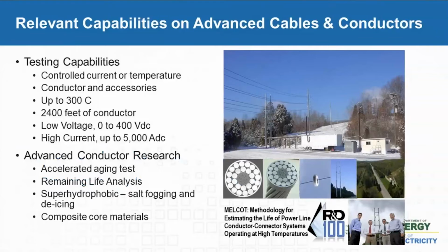Here is a highlight of relevant capabilities and research activity seen at ORNL. There is an outdoor test facility dedicated to power line conductor accelerated testing. It can test 2,400 feet of conductor. The system can inject as high as 5,000 amperes of current and test the conductor and the devices at extremely elevated temperatures. ORNL has also been working on conductor and connector systems for more than 10 years, with project milestones including one R&D 100 award in 2008.